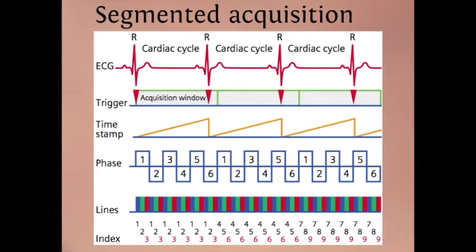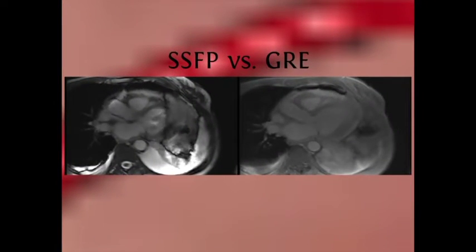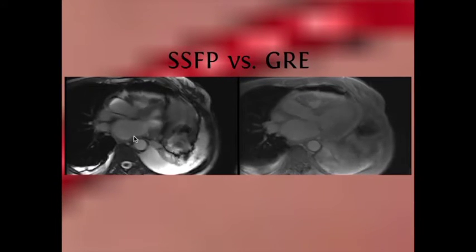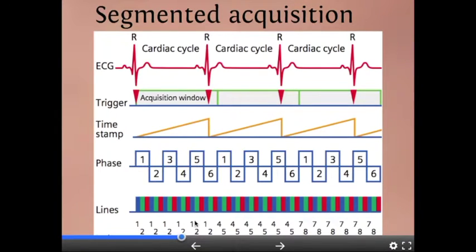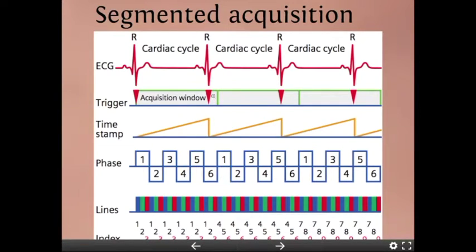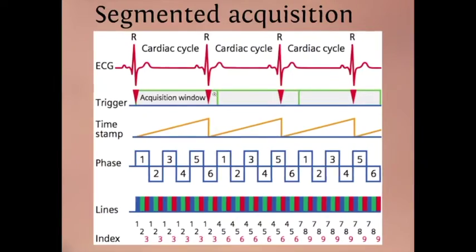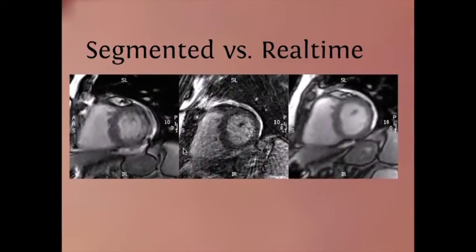The segmented acquisition takes somewhere between 8 and 15 heartbeats to acquire data, but it looks like we're seeing one heartbeat — we fuse all that data into one representative heartbeat to get the spatial resolution we need. Different phases have different lines of K-space per phase. There's no way to fill all lines for all phases in one cardiac cycle, so the strategy is to decrease lines of K-space. Here we have images that are segmented and some that are real-time.